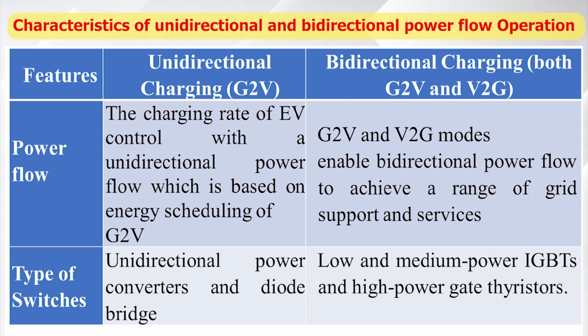Mostly in the case of unidirectional chargers, people are using a diode bridge rectifier followed by one PFC converter, which may be a boost converter, and a DC-DC stage. So, using this control, people are doing PFC, power factor improvement, and they are using these two stages. However, in the case of a bidirectional charging system, we require controlled switching. So, for the AC to DC stage, an IGBT-based inverter, or for low power applications we can utilize MOSFETs, but for medium or high power applications we have to utilize IGBTs and high power gate thyristors.